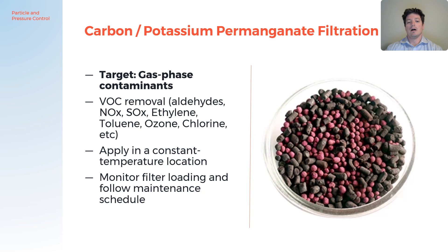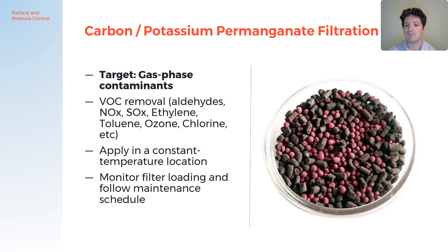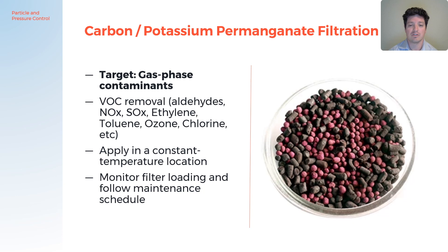It's also critical to apply this technology at a constant temperature location within the air handling unit — typically downstream of the cooling coil. This is because the media behaves differently under different temperature and humidity conditions. If it's loaded with VOCs and near the end of its life and there's a big spike in temperature or humidity, it can actually off-gas and dump those contaminants back into the airstream going into the lab — which is absolutely not what we want. Proper placement of this filtration technology is therefore critical.